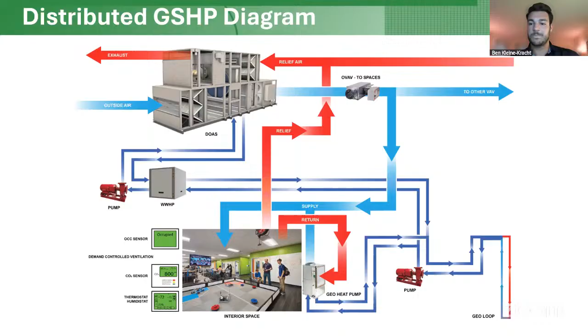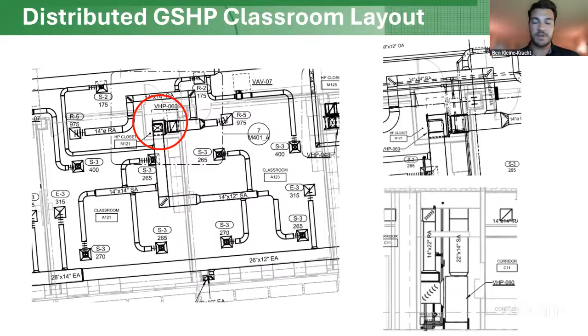Again, a little closet slide. I typically take little squares and litter them all over the floor plan, and we try to find homes for them. You can also put more than one in a room. I've seen them do a mechanical room per wing, central to the wing, with 5 or 6 of these heat pumps, then route them to those spaces. So it doesn't have to be just one in each closet, we can buddy them up. Typically we use 4-ton heat pumps per 2 classrooms, so 2 tons per classroom, 4 tons total.